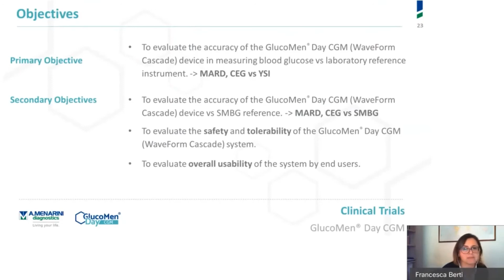The primary objective of the study was to evaluate the accuracy of the GlucoMen CGM device in measuring blood glucose versus a reference instrument, which was YSI. The secondary objectives were to evaluate the accuracy of the GlucoMen CGM versus an SMBG reference. In both cases, the endpoints were the calculation of MARD and consensus error grid analysis versus YSI and SMBG, and also to evaluate the safety and tolerability of the GlucoMen CGM, and to evaluate the overall usability of the system by end users.